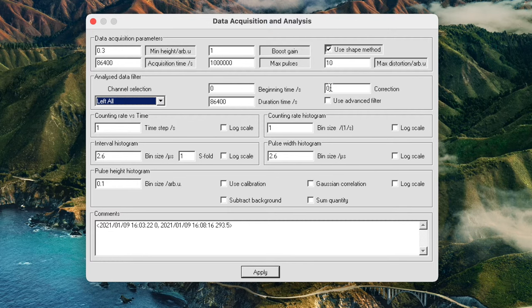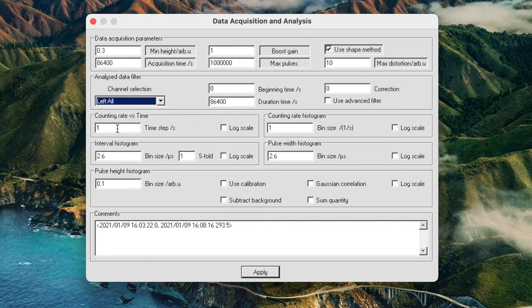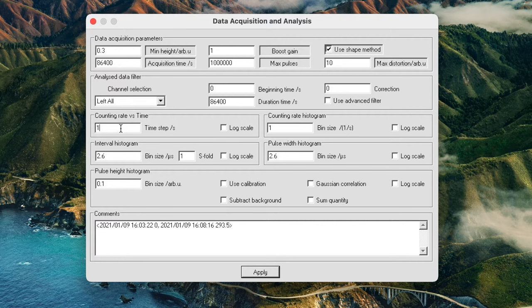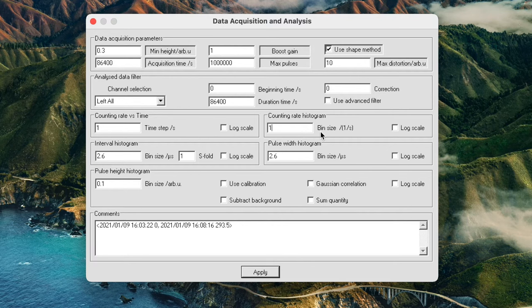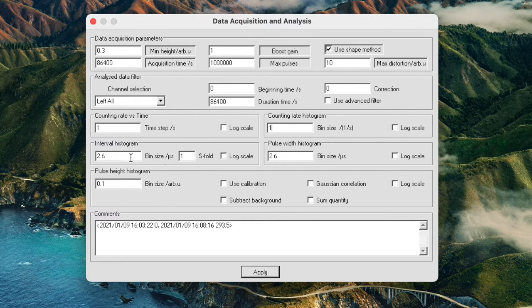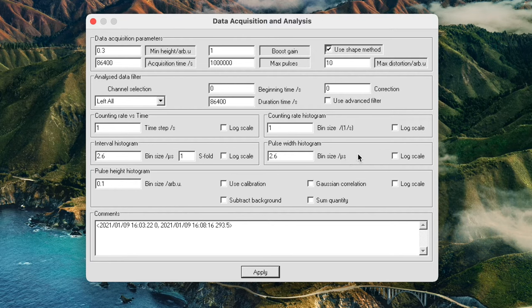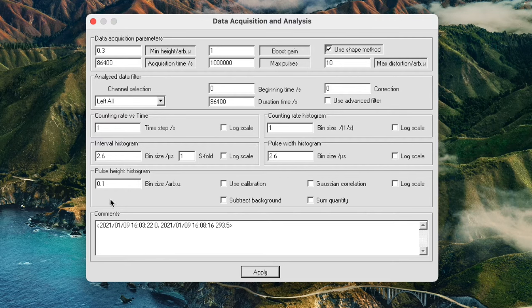The next field is the advanced filter and we won't be covering that in this video. Counting rate versus time gives you a histogram of count rate, basically how many counts per second. You can adjust the bin size and it's by default set to one second but if you set this to 60 seconds then you will get counts per minute. Then you have your counting rate histogram which is a histogram of what your count rate is rather than counts per second. Interval histogram is the histogram of the time between pulses. And the pulse width histogram shows you the pulse width.